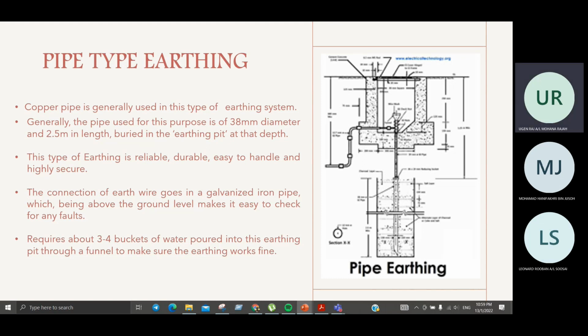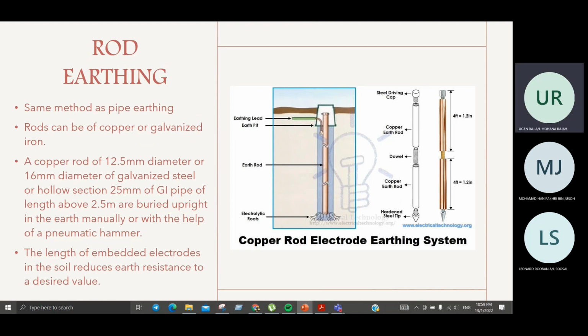Okay, so the next method is rod earthing. Rod earthing is the same as the pipe earthing method. The rod can be a copper or galvanized iron rod. A copper rod of 12.5 mm diameter, or 16 mm diameter of galvanized steel, or a hollow section of 25 mm of GI pipe with a length above 2.5 meters, is buried upright in the earth manually or with the help of a pneumatic hammer. The length of the electrodes in the soil reduces earth resistance to a desired value. So these are the 3 methods that can be used for earthing.